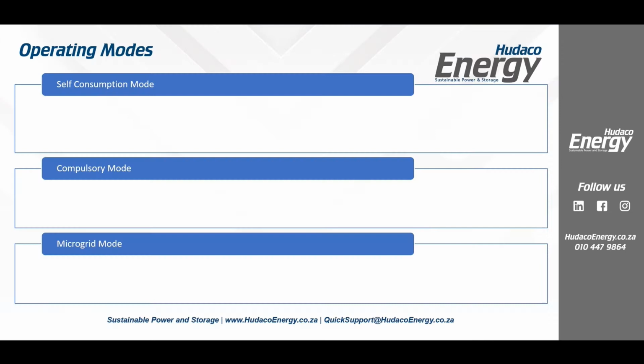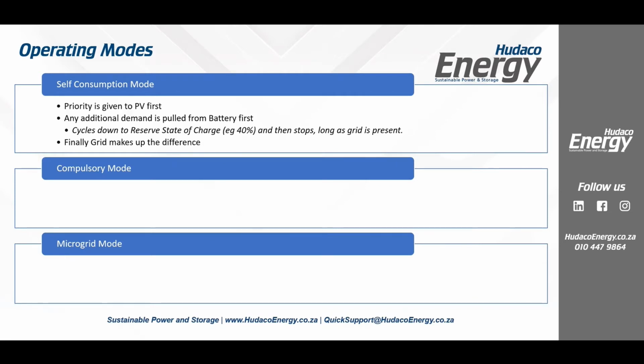Okay, inside the software of the inverter, we normally run in one of 3 operating modes. There are actually 7 that are available for selection, but for South Africa, we only use 3. The most common is self-consumption mode. Self-consumption mode is very simple. The first thing we prioritize is solar power over everything else.